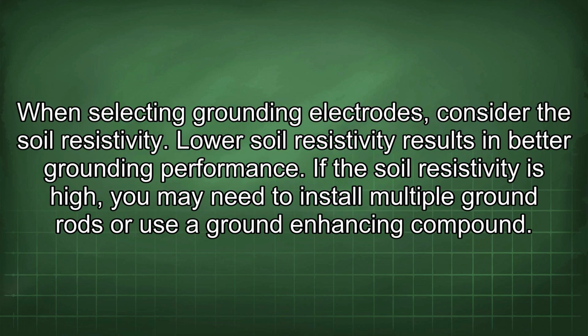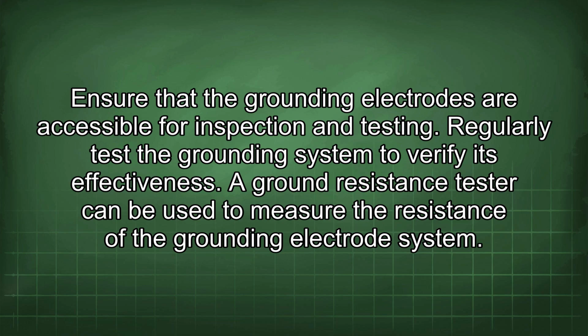When selecting grounding electrodes, consider the soil resistivity. Lower soil resistivity results in better grounding performance. If the soil resistivity is high, you may need to install multiple ground rods or use a ground enhancing compound. Ensure that the grounding electrodes are accessible for inspection and testing.